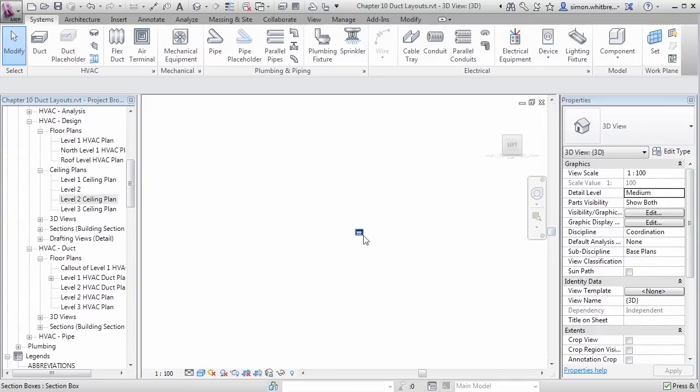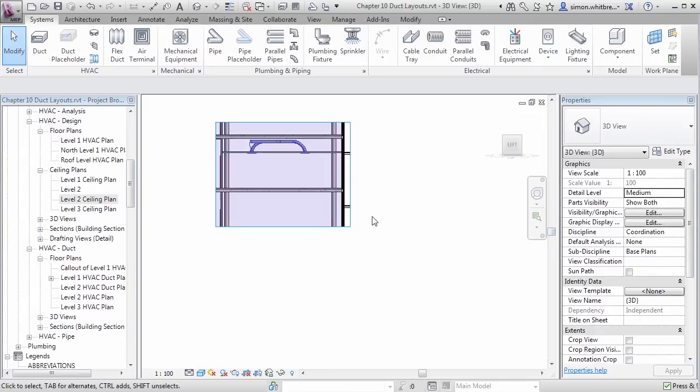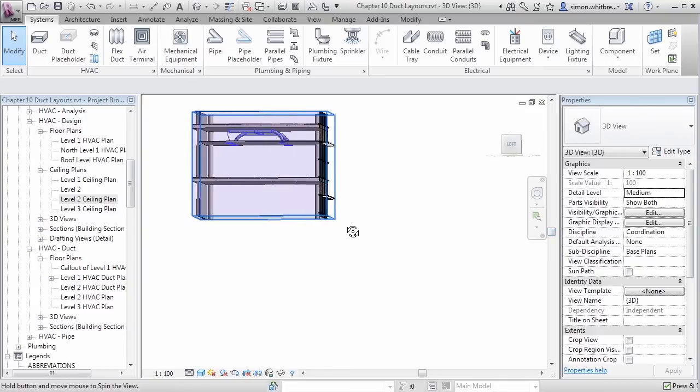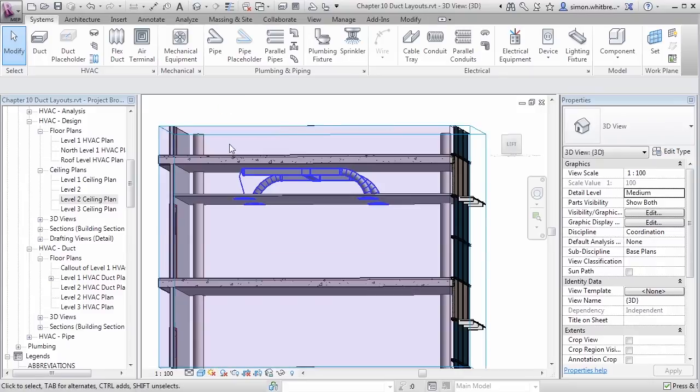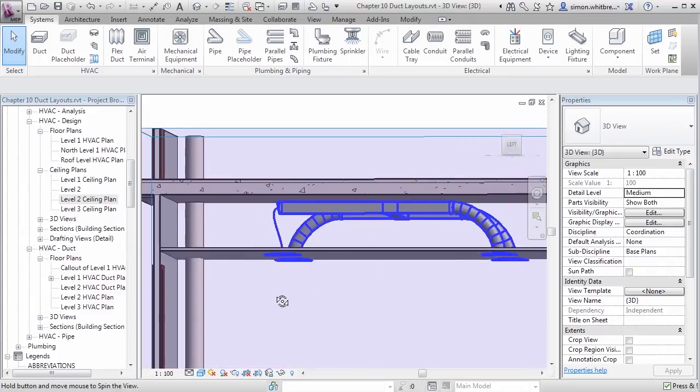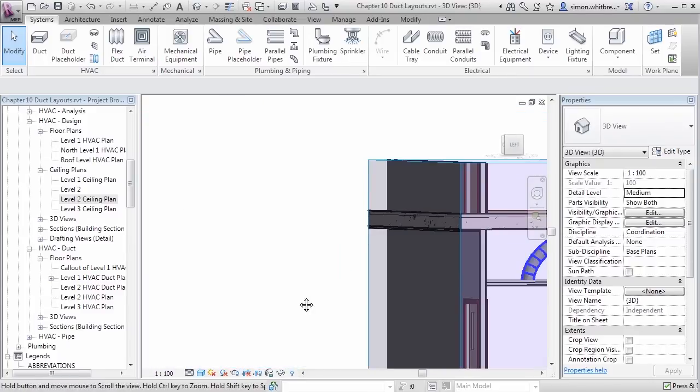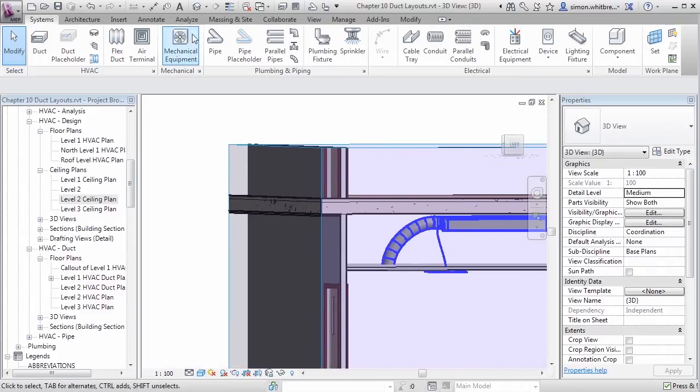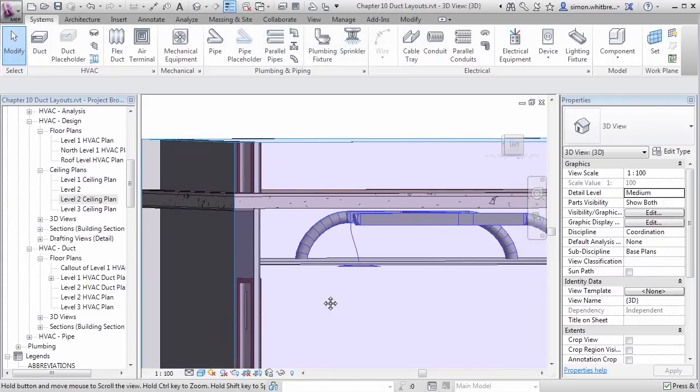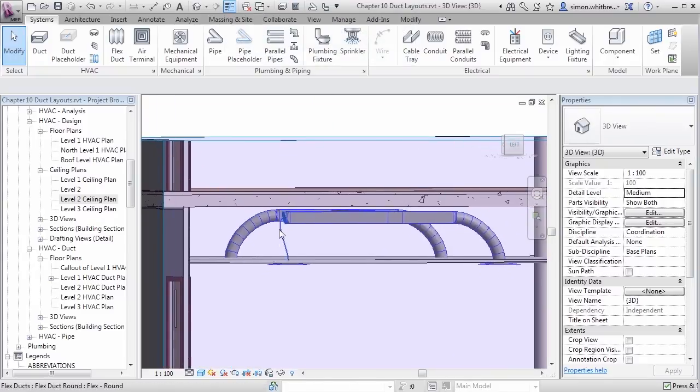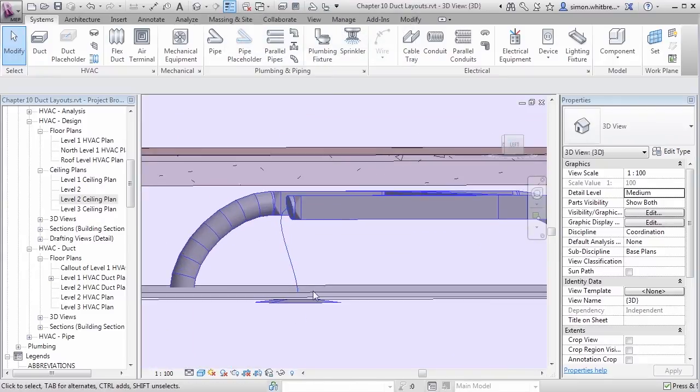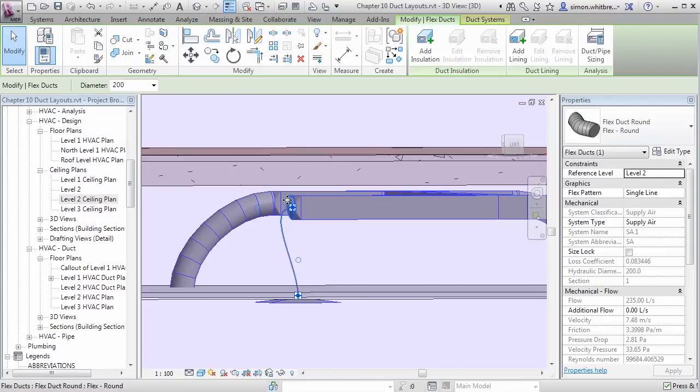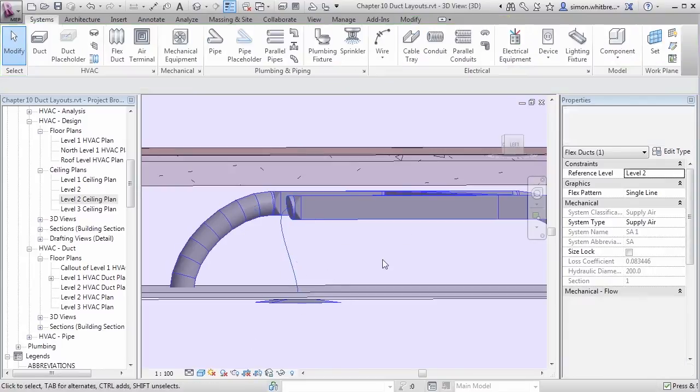This has now cropped my entire 3D view, but it allows me to see how the design works with the rest of the services. It also allows me to pick up any errors, like this flex duct that isn't working. Its bend is too great and that is why we can only see a single line.